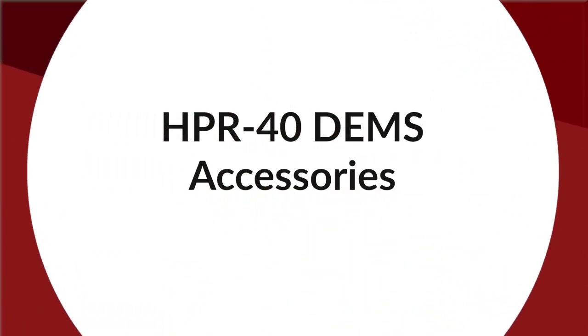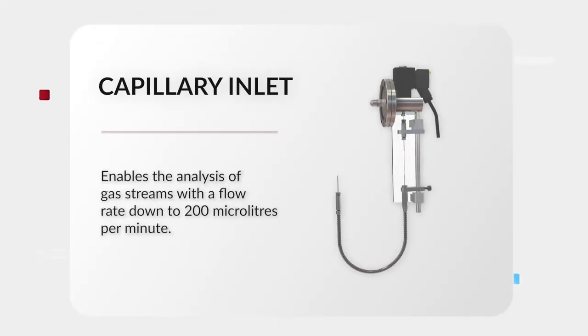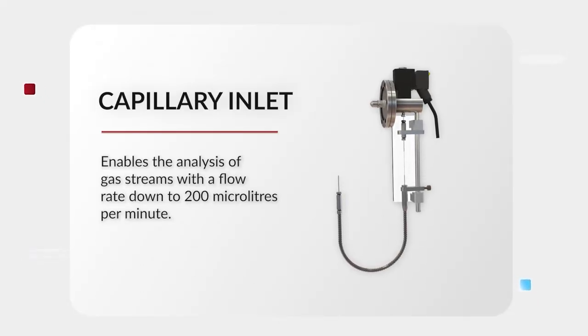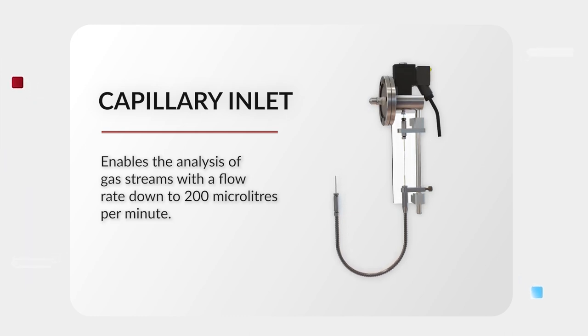The HPR-40 DEMS can also be configured with a range of accessories to expand its versatility, including a capillary inlet, which enables the analysis of gas streams with a flow rate down to 200 microliters per minute.